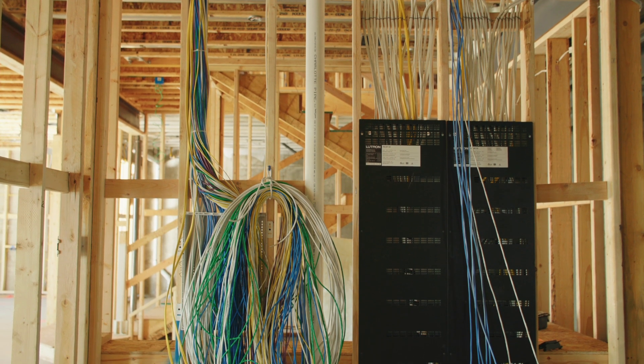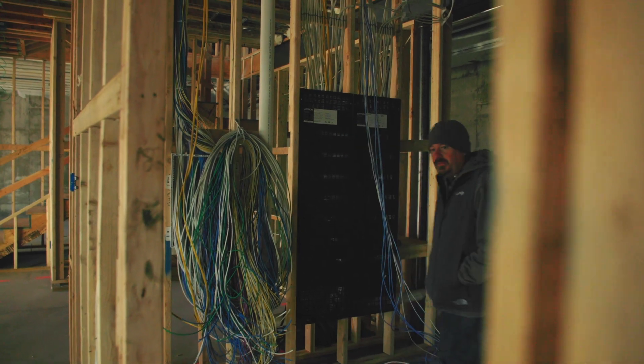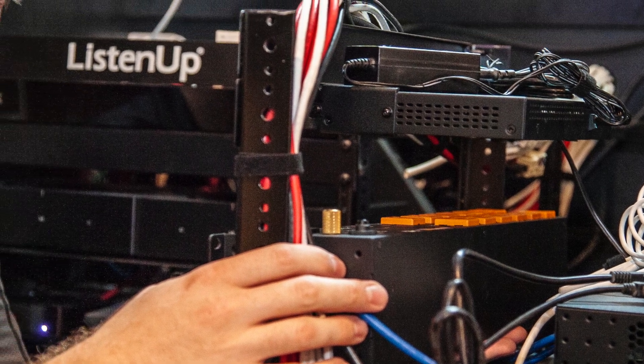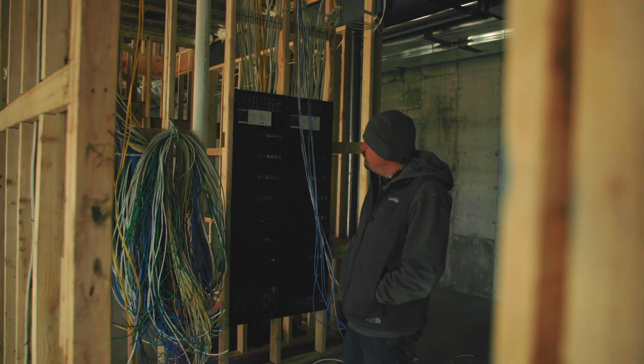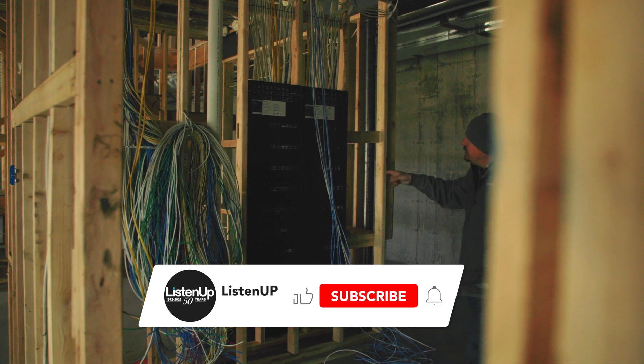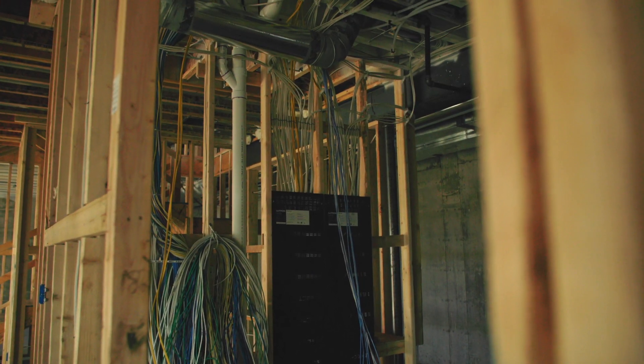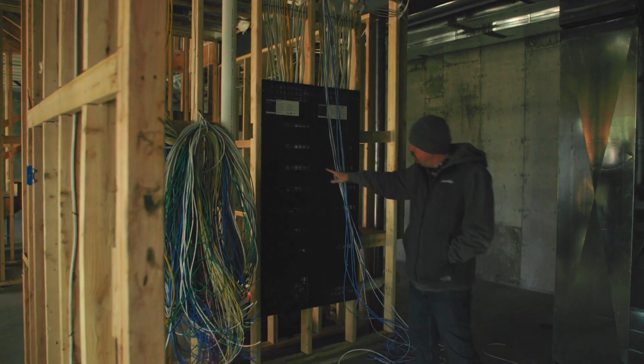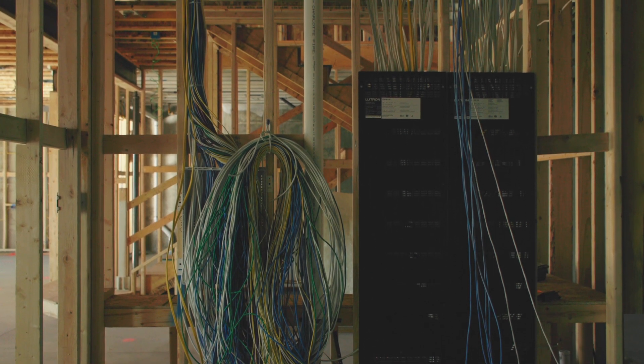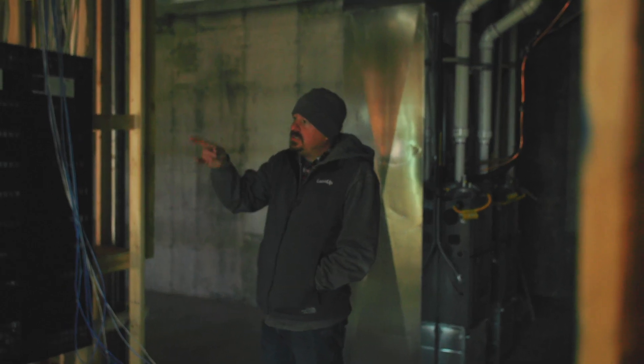Then we've got the main brain and heart of the system. We've got all our low voltage wiring coming down here, and we're going to have a main rack of equipment so that everything can stay at proper temperature as well as be easily serviceable. We have the two main Lutron lighting panels. These panels are where modules go in to control the lighting throughout the house. This is what 'centralized' means — all the control for the actual specific lighting loads are here. And this is what allows us to get away from all the wall acne of multiple switches and go down to just single keypads.